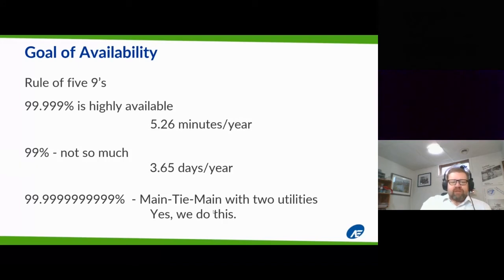But not a lot of facilities are going to have dual mains, so they will suffer from a single point of failure. You might remember that from the resiliency presentation earlier. Louis had mentioned that we forget that transformer is a single point of failure at the front of the plant. If that transformer does happen to fail, the whole site goes down, and it will take days or months to replace it.